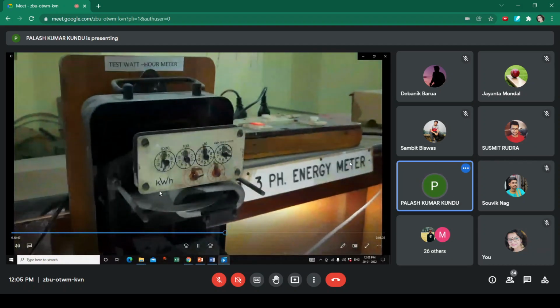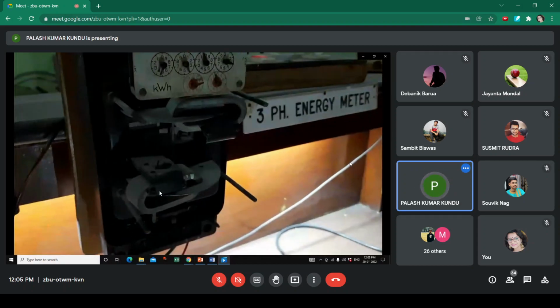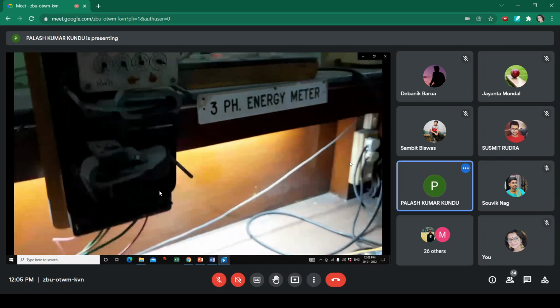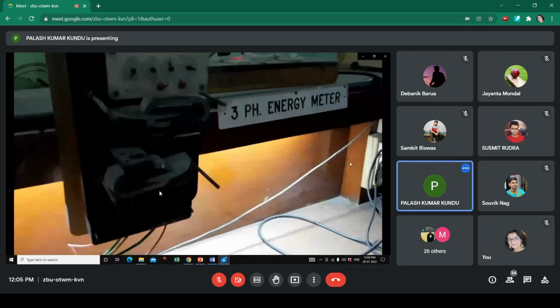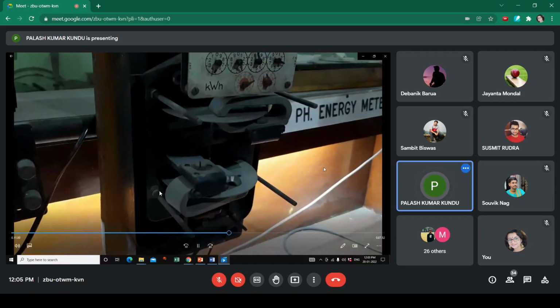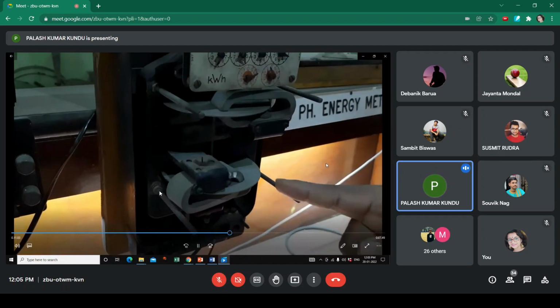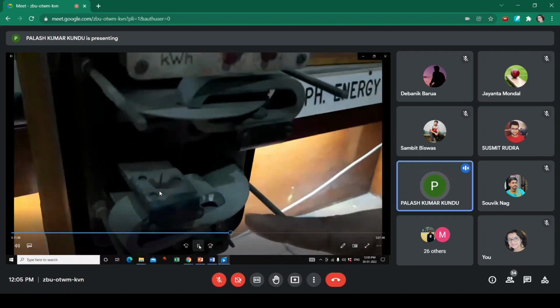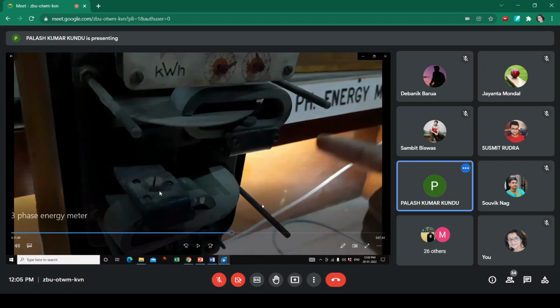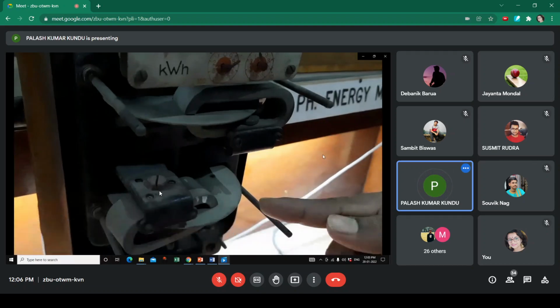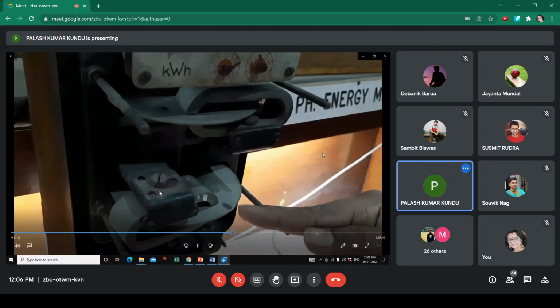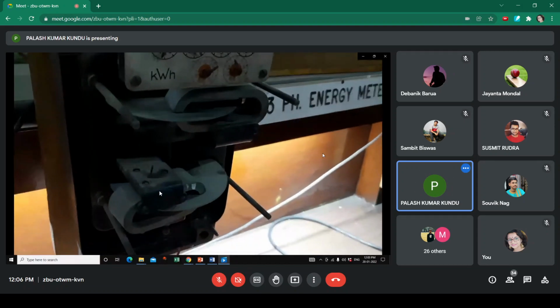As I told earlier, for 100% load and unity power factor we will take 40 revolutions of this disc. You can check only one disc. So how do you check that? You can see that there is a black mark. By counting how many times the black mark passes during rotation, each time the mark comes back to the same place, that is one complete revolution. That way you have to count 40.